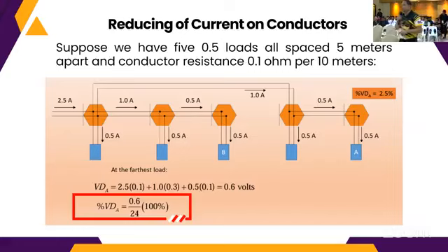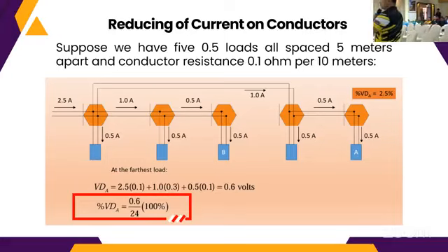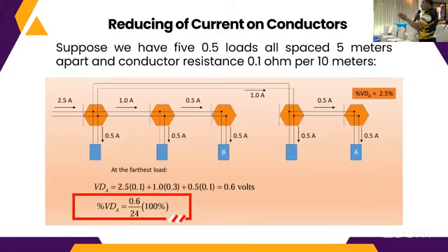Okay, so there's another example. We have 2.5. Then we have 0.5, then 1, nag-split na sila. 1, then 1 sa kabila, papunta doon sa A. Then 1, 0.5, 0.5. Then calculate the voltage drop at A. So that is 2.5 times 0.1 plus 1.0 times 0.3 plus 0.5 times 0.1, which is equal to 0.6 volts. So 0.6 divided by the supply voltage, that is 24 volts, times 100%. So our voltage drop is 2.5%.